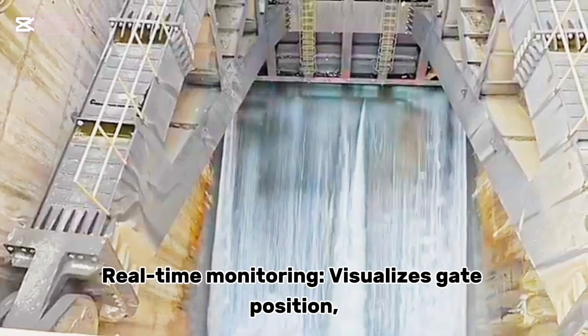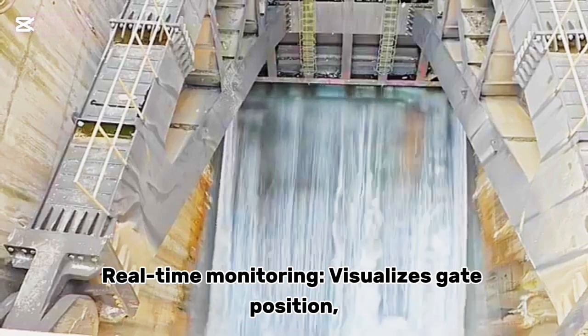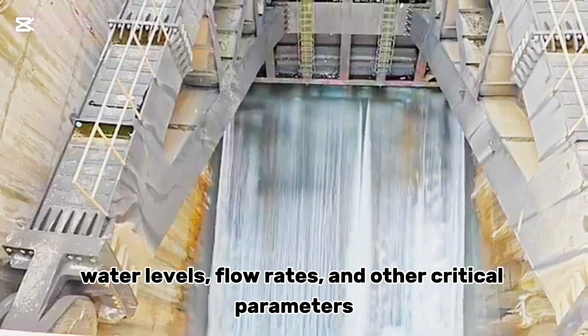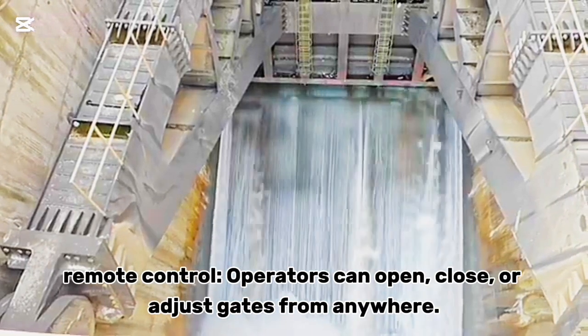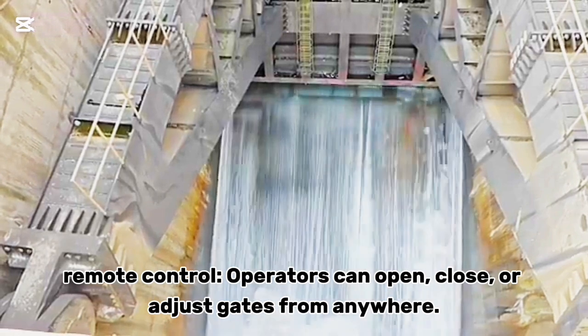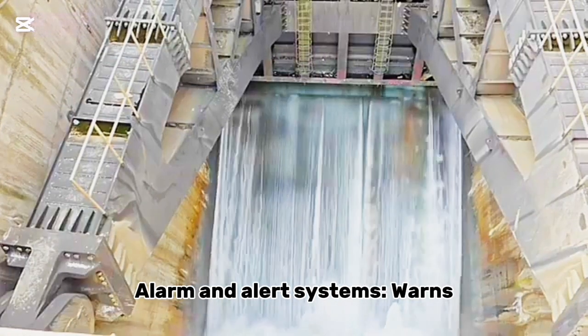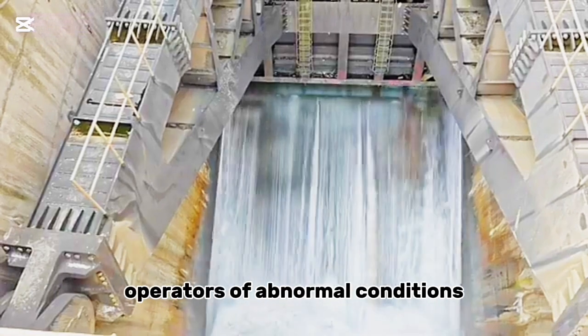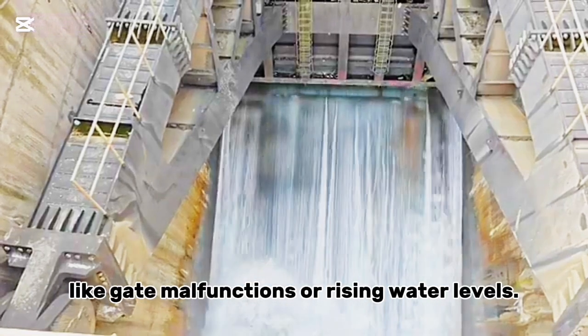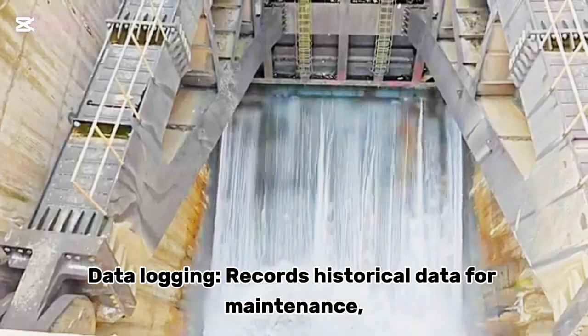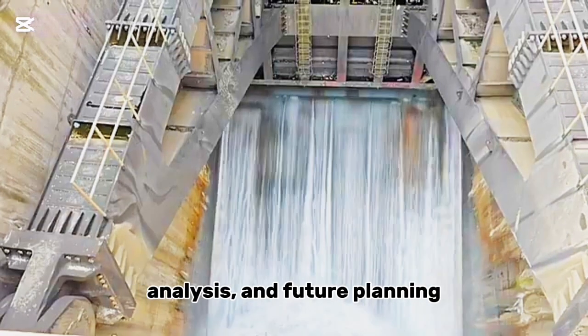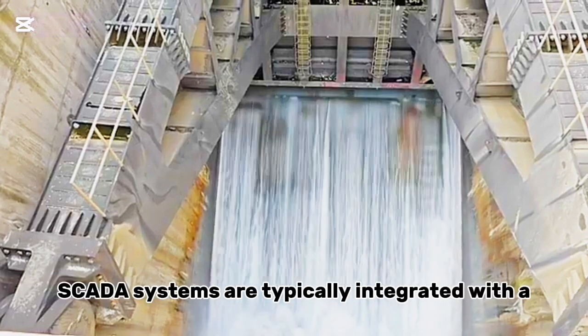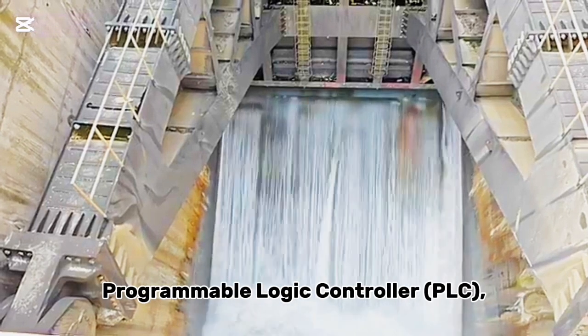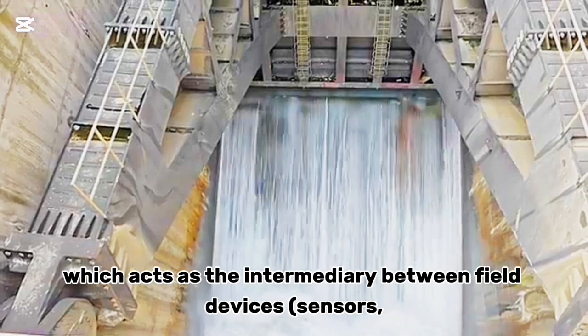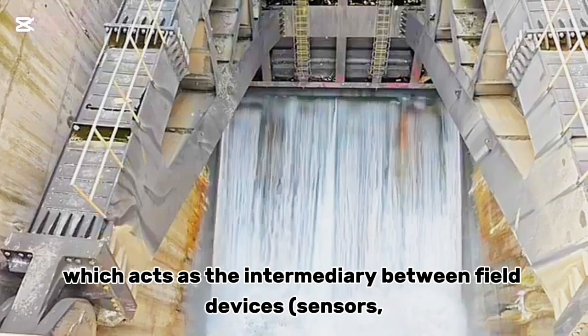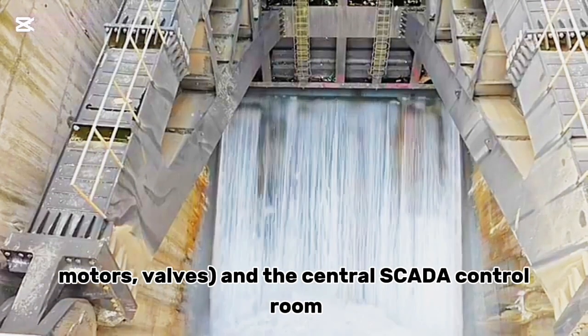SCADA provides real-time monitoring, visualizes gate position, water levels, flow rates, and other critical parameters. Remote control. Operators can open, close, or adjust gates from anywhere. Alarm and alert systems warn operators of abnormal conditions, like gate malfunctions or rising water levels. Data logging records historical data for maintenance, analysis, and future planning. SCADA systems are typically integrated with a programmable logic controller (PLC), which acts as the intermediary between field devices, sensors, motors, valves, and the central SCADA control room.